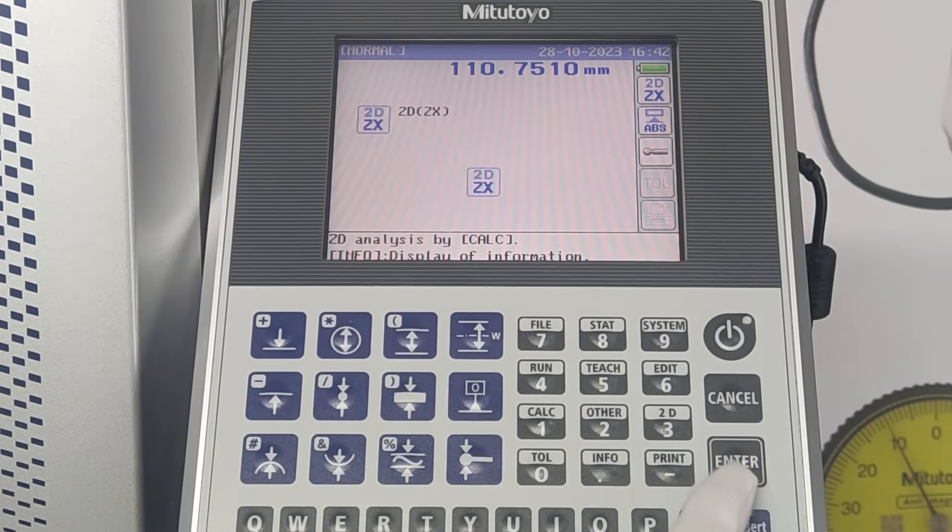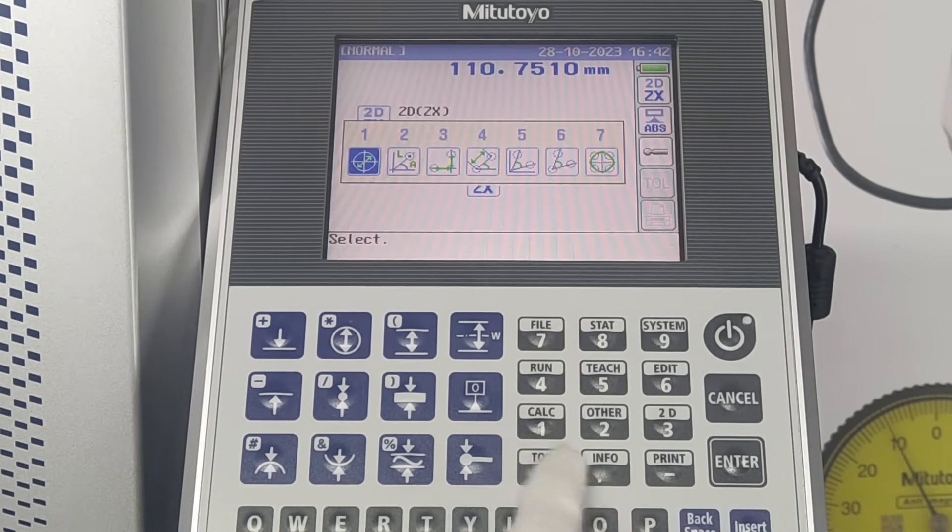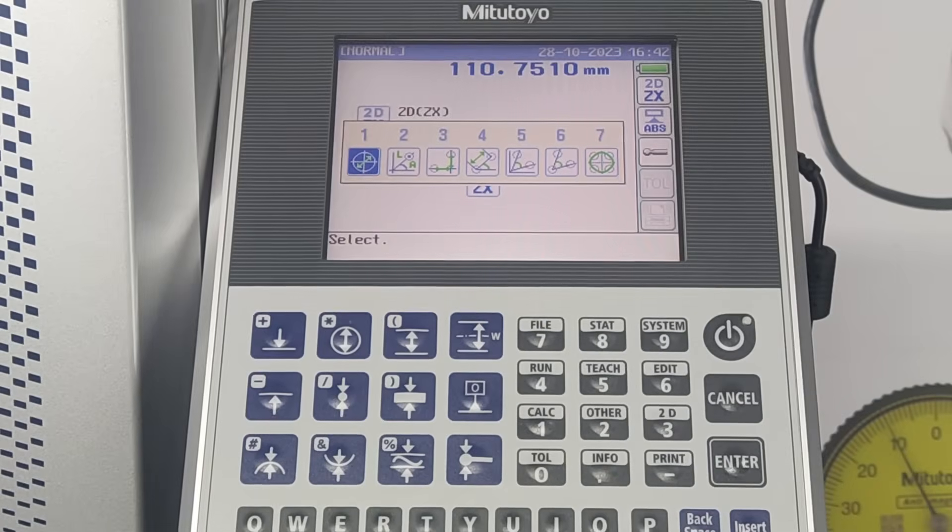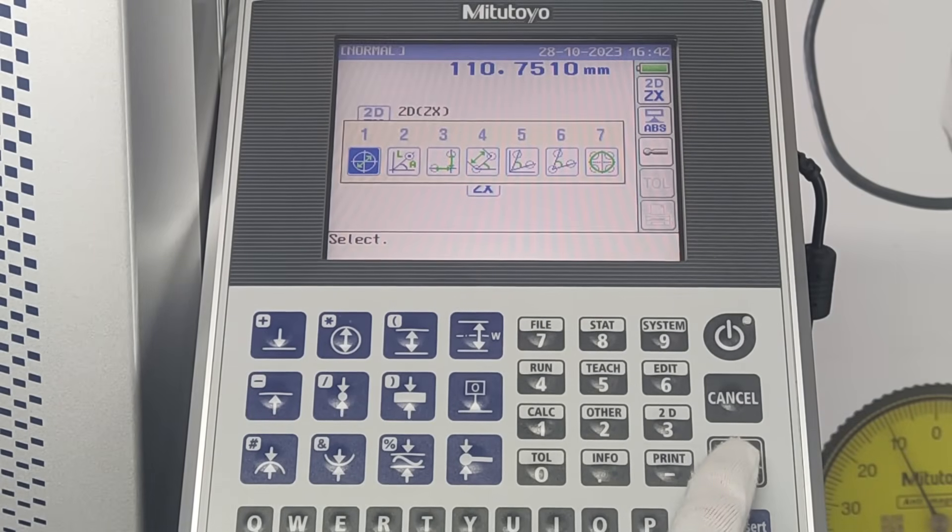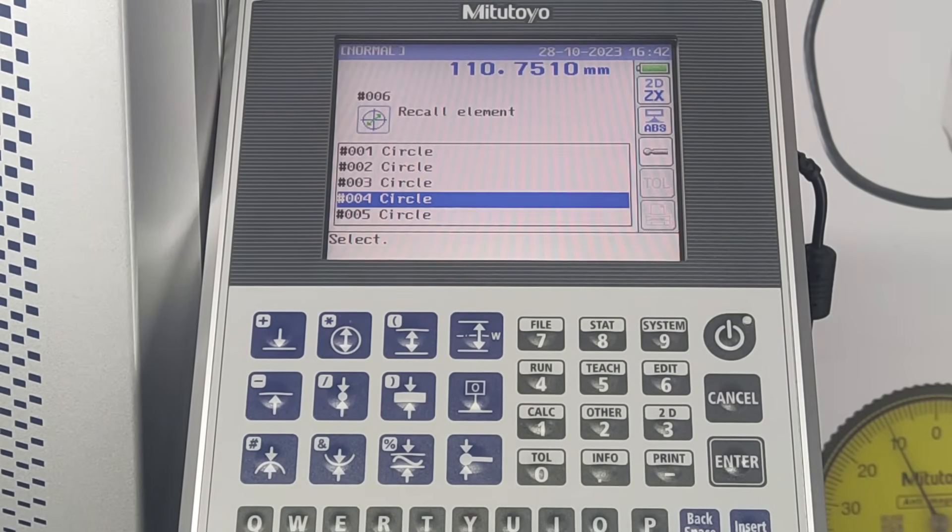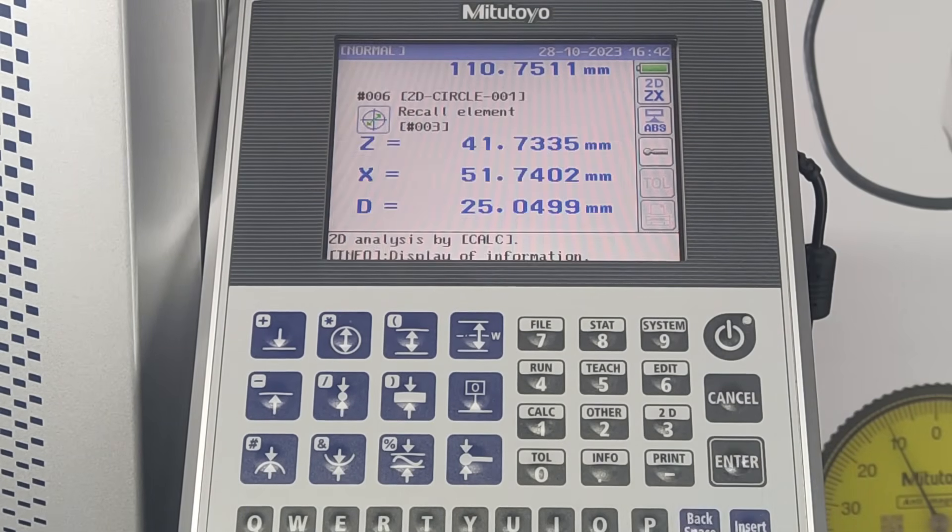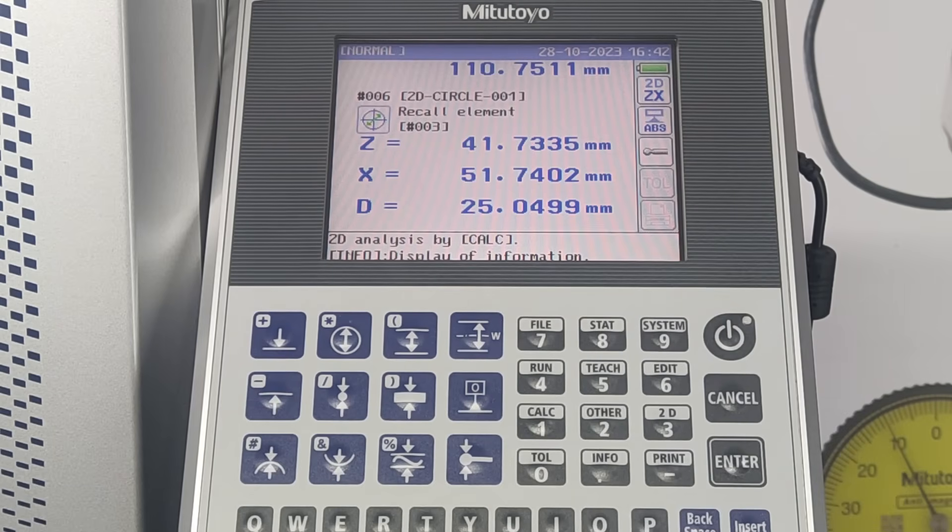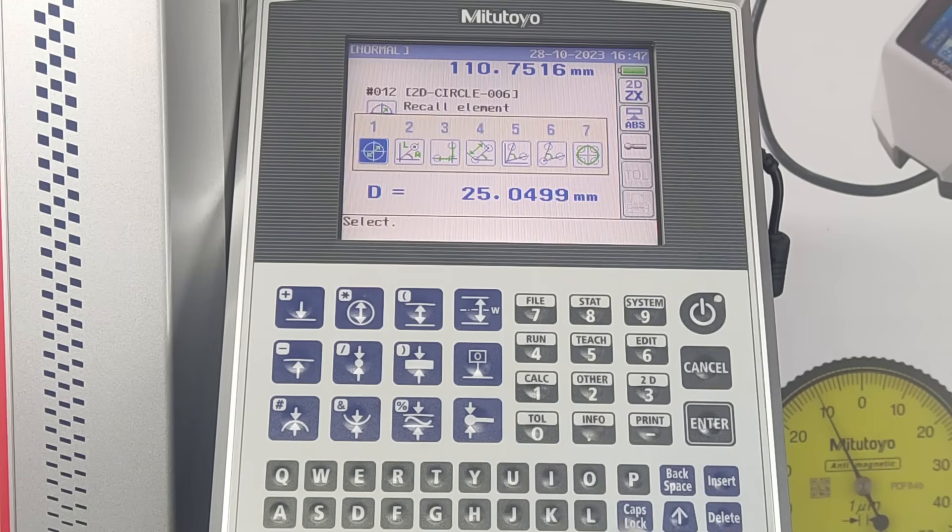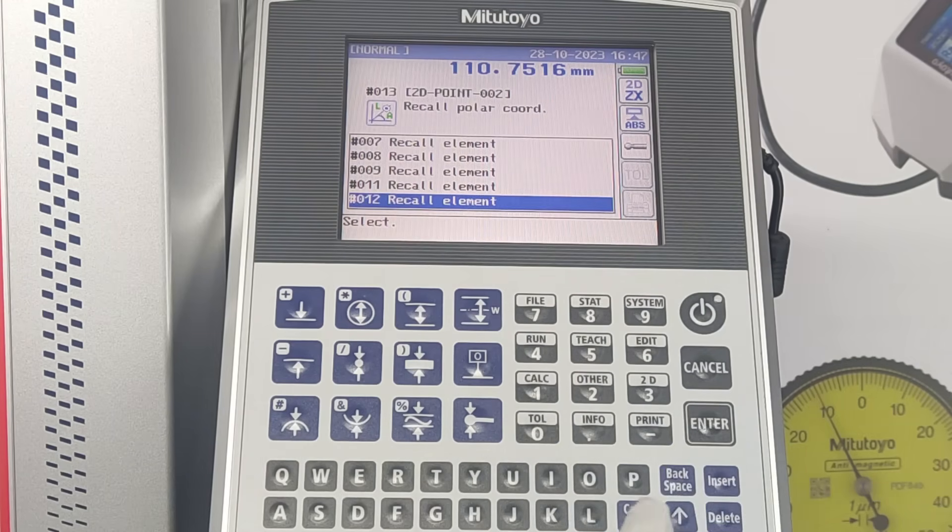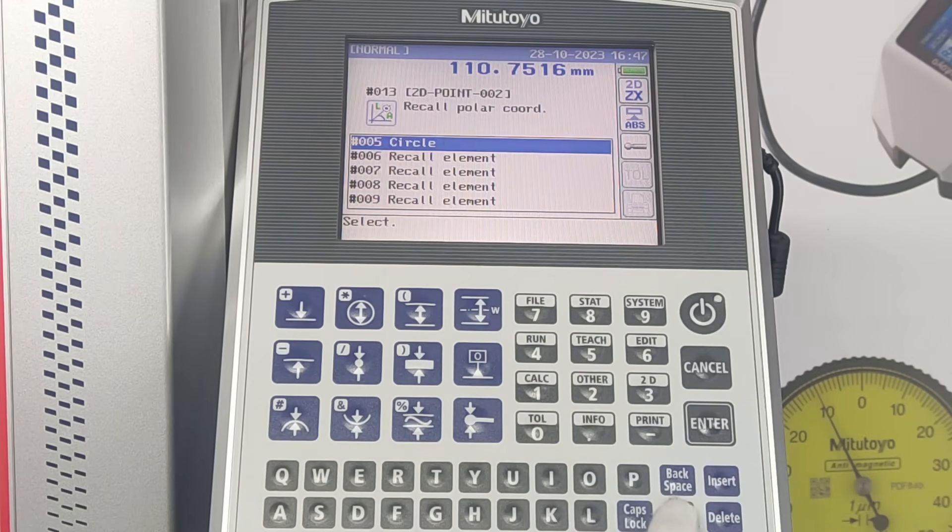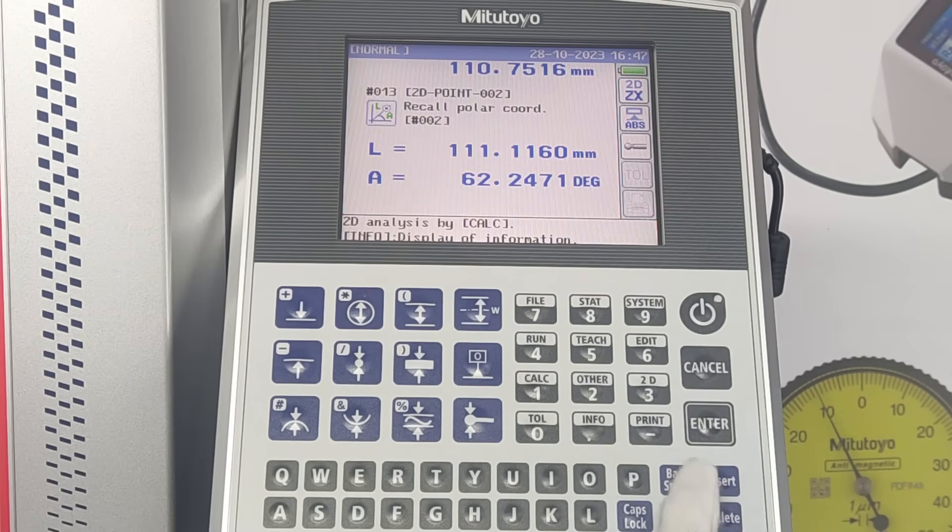Measured data result can be viewed. Press calculate to view every 2D option. The first one is to measure diameter. Select the required circle. Z and X are the coordinate axis and D is the diameter in mm. The second option is to view polar coordinates. Select the required circle. L and A can be measured. L is the radial distance from origin and A is the angle.